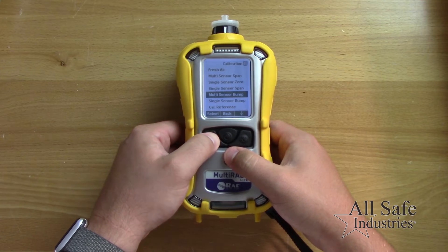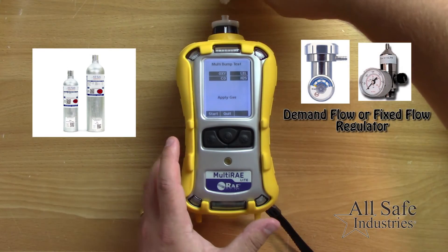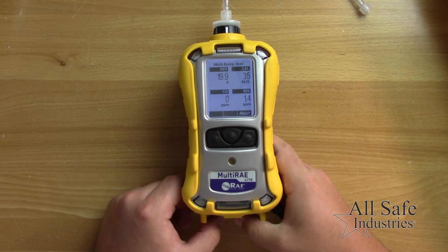The display will show the sensors available with a prompt to apply gas. Connect your gas to the inlet and press the Y plus key to start. You may need more than one cylinder to bump check all the sensors in your MultiRAE.